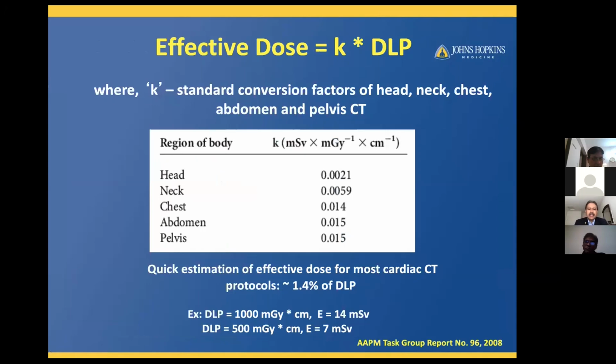These are the standard K factors published as of now, and we continue to use these K factors, even though there are some limitations on the K factor, because these were developed for scanners prior to multi-detector CT, but we still use them for easy comparison. So basically, you take the DLP from this patient, and if you multiply by this K factor, you arrive at an effective dose, an approximate effective dose.